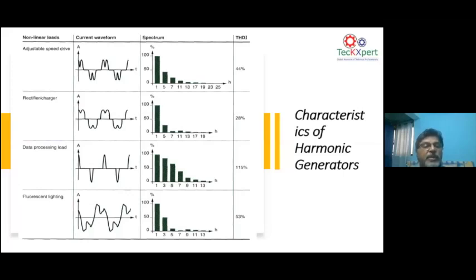rectifier load, for example a VFD, the current harmonic shape is something like this. That means it produces 5, 7, 11, 13, and the total harmonic distortion by a VFD. This VFD is considered 44% because it may have a line reactor at the input.